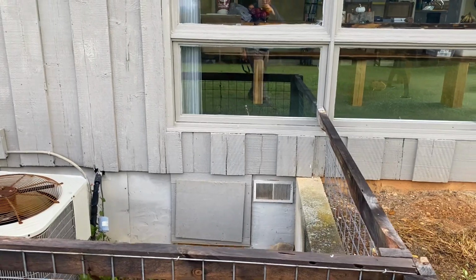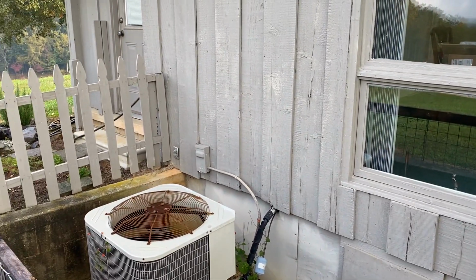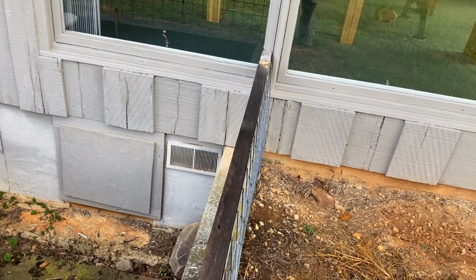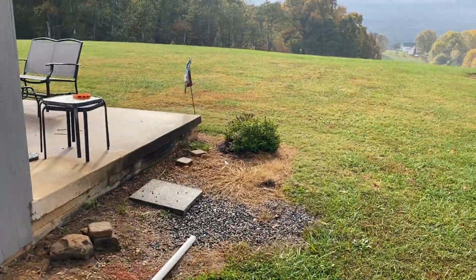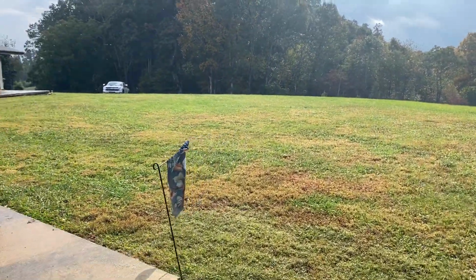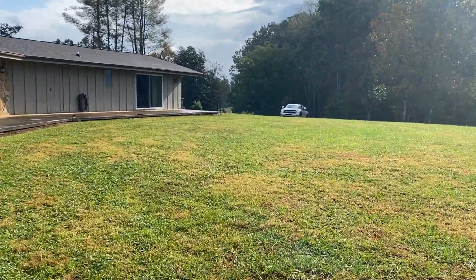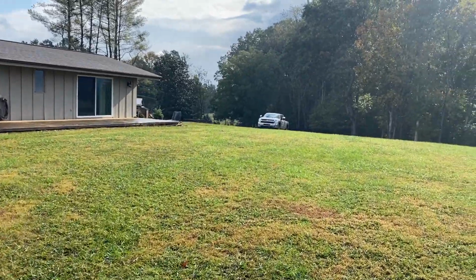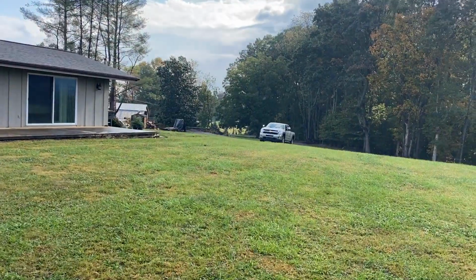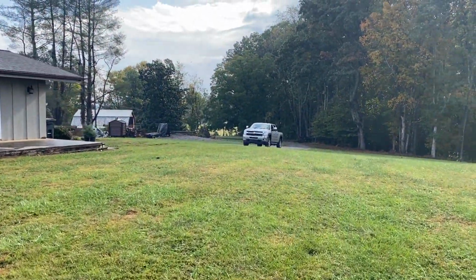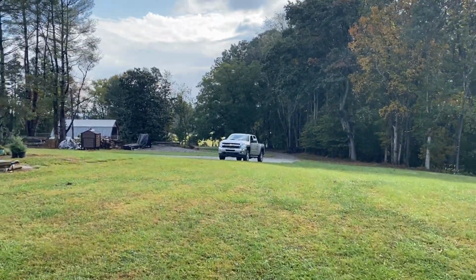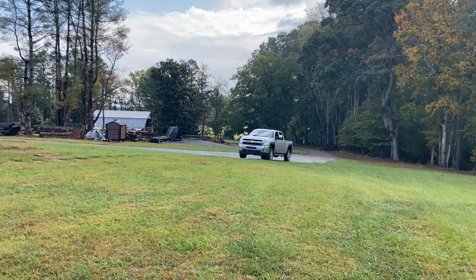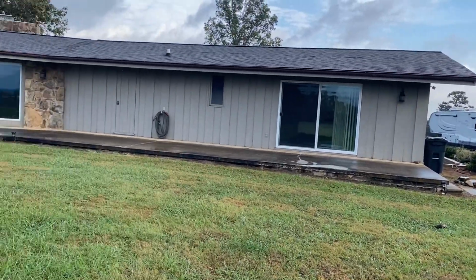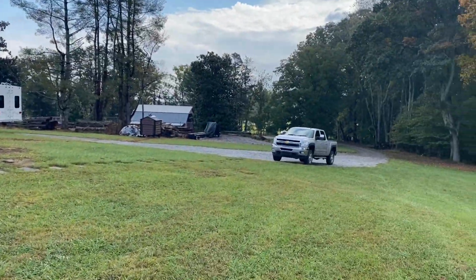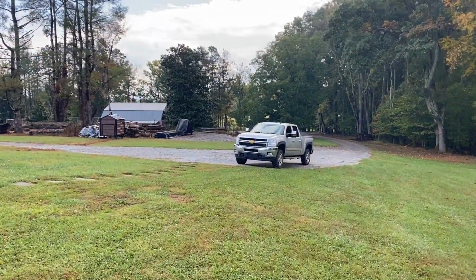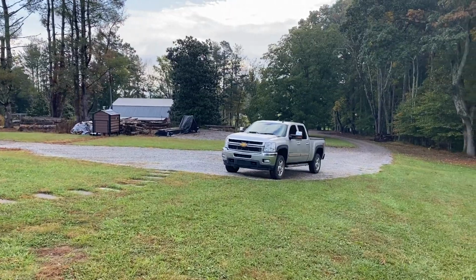I've got to get through and see what I'm facing to physically install it at the air handler. It can go in either the supply or return duct. It makes little difference. The only difference is that if you put it in the return duct, you're blowing warm or potentially hot air across the fan motor, and fan motors apparently don't like to be too warm, which I don't really believe, because if your house was at 80 degrees, you'd have 80-degree air flowing over it anyway since it's a closed loop system. If I'm generating 90 or 100, I don't think the fan motor would care. But we'll see. I'm going to try and put it in after the fan, and if I can't, I'll put it in the return side.